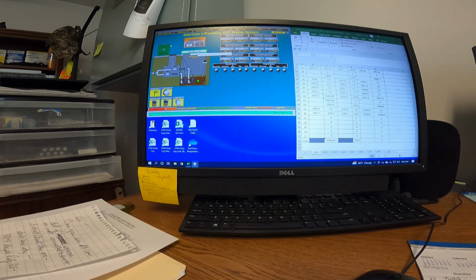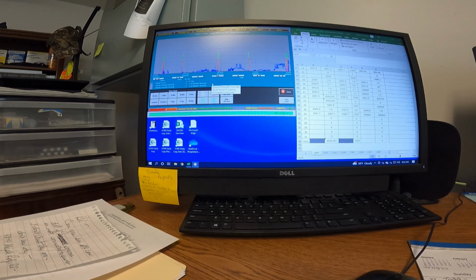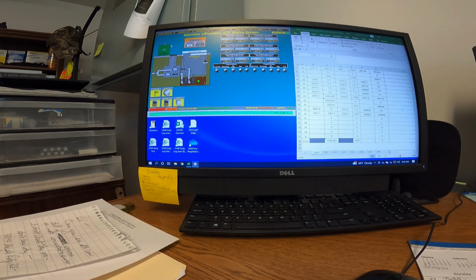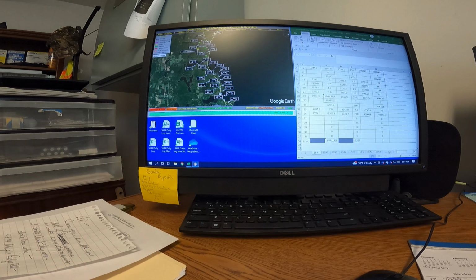And if we want to go here, this is the trend line. And now you can see where I was running the pumps here. Now you can see what that transducer was doing. See how it was bouncing all over the place and coming up and down here and here. Now this should settle out and start looking normal. And let's go look at another lift station and see what normal looks like.